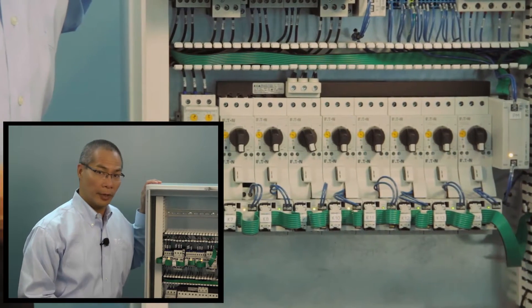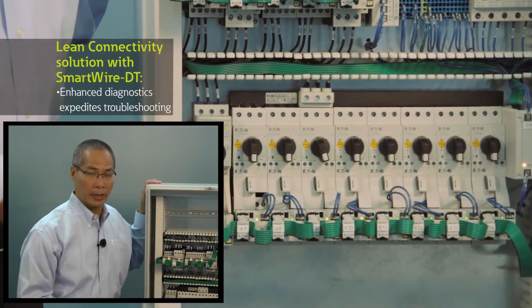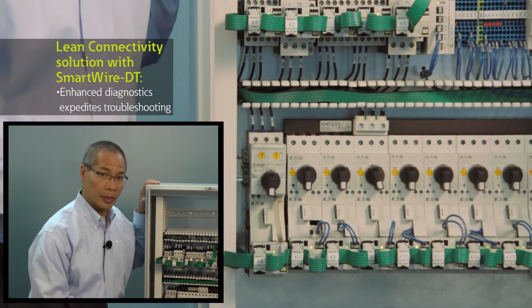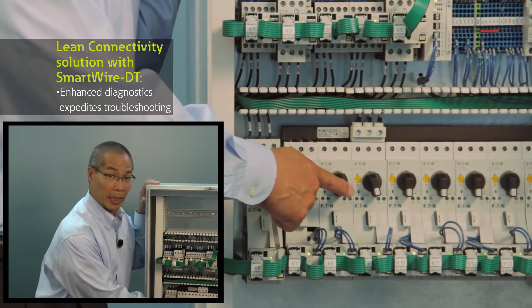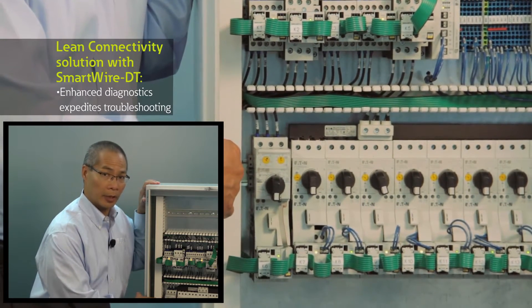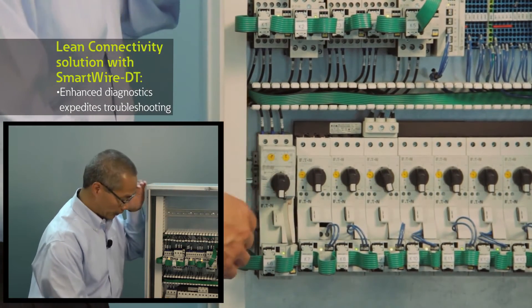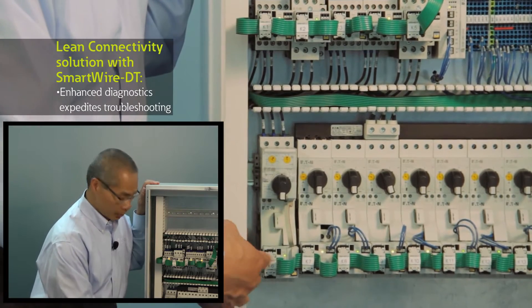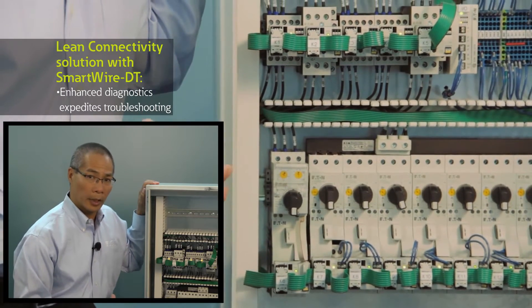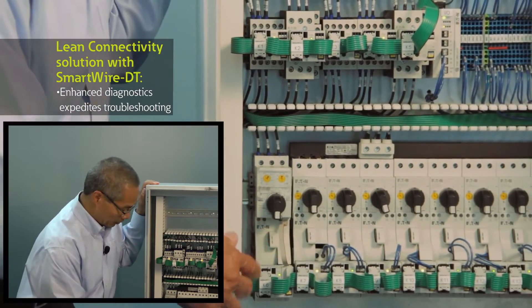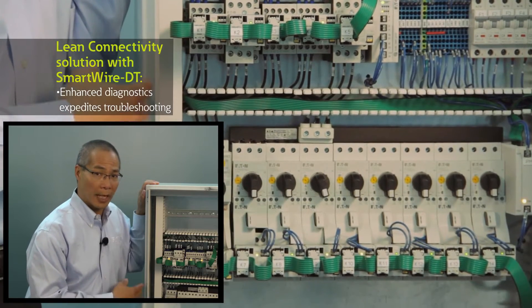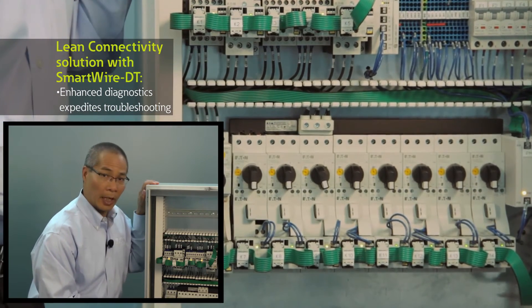With SmartWire DT, I can do a number of things, and one of those is to get diagnostic information over the network. If you'll notice, I have two types of manual motor protector units inside this cabinet. One is our standard electromechanical manual motor protector unit, and on the left-hand side here, you'll see an electronic manual motor protector unit with an interchangeable trip unit. With SmartWire DT, I can actually tap into the electronics on that unit, and I'm able to monitor the motor current that's coming out of this motor connection. I can also monitor the status of the MMP and its trip condition.